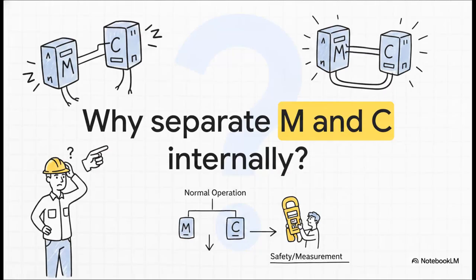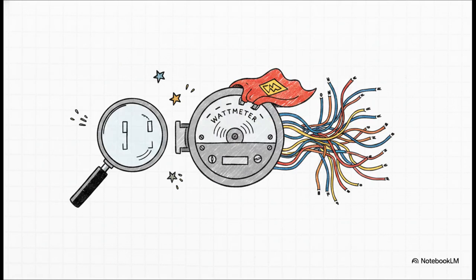So you've got to wonder, if these two terminals basically always need to be connected to get a normal reading, why on earth didn't the manufacturer just connect M and C internally at the factory? Why intentionally leave them physically separated on the outside of the casing and make the user do the extra work? Well, it turns out keeping them separate gives engineers a total diagnostic superpower.